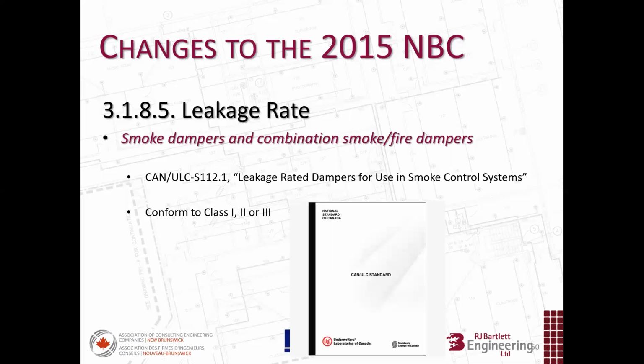We now have some additional information on the leakage rate. This, I believe, was triggered with the inclusion of smoke dampers in the 2015 building code, but it's also carrying over to some requirements on door leakage in specific situations. But for smoke dampers, we have requirements for leakage and certain performance, and it's defined by this CAN ULC S1121 standard, leakage rated dampers for use in smoke control systems.